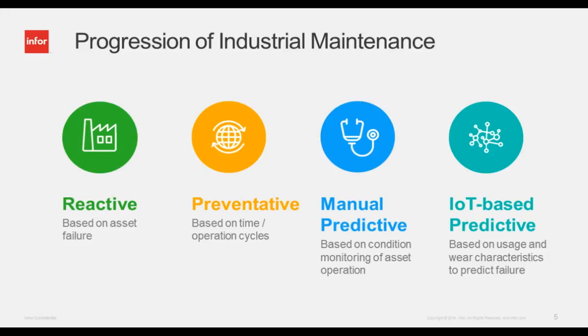Now, with the advent of IoT devices, you can take advantage of real-time sensors installed on equipment. IoT-driven sensors attached to factory equipment record and compile millions of data points around the clock, providing real-time monitoring for pending failures. Sensors embedded in equipment check for abnormal conditions and can trigger work orders when safe operating limits are breached. Most equipment today has built-in sensors, and older equipment can be retrofitted. Companies can then feed this data into predictive models to determine when something is about to fail or what the remaining useful life is. This lets managers know which equipment needs maintenance, so work can be better planned, systems stay online, and tasks are performed only when needed.